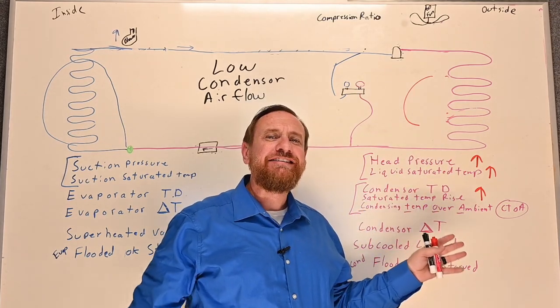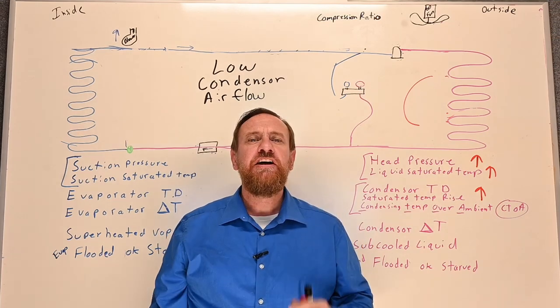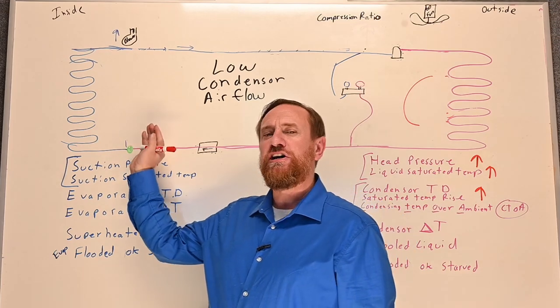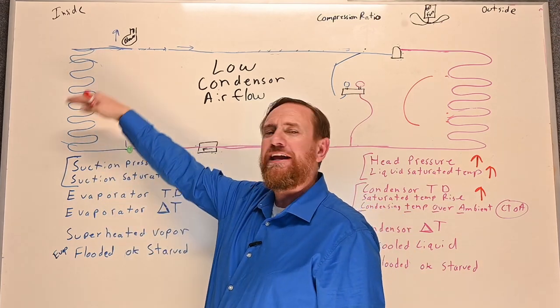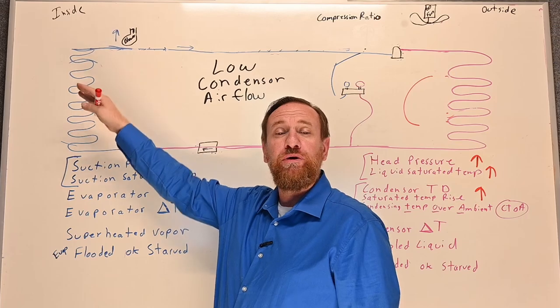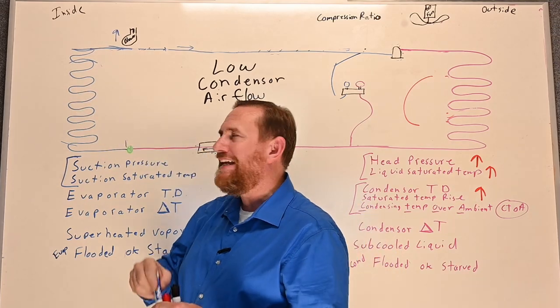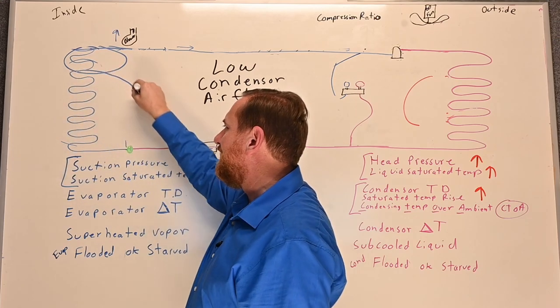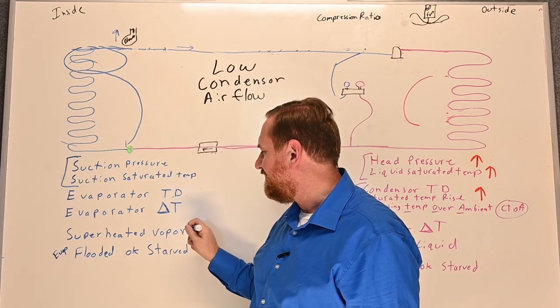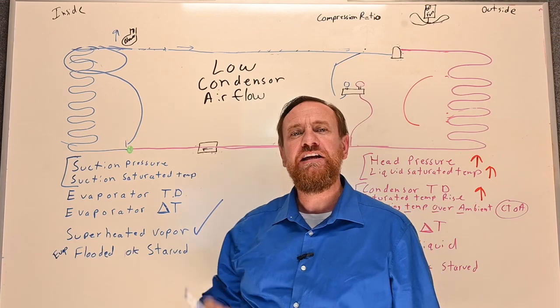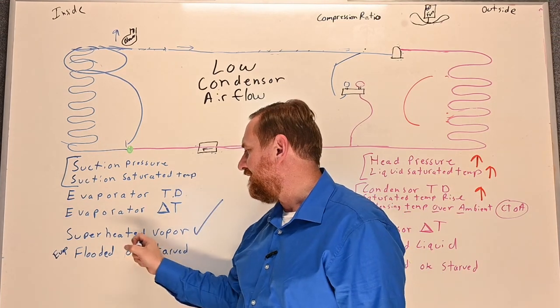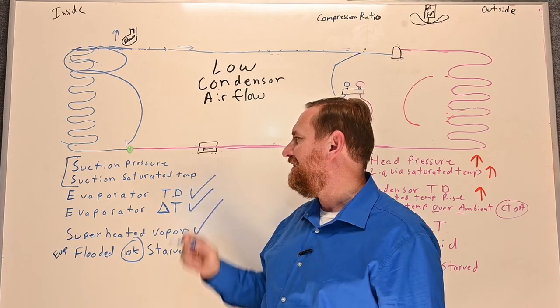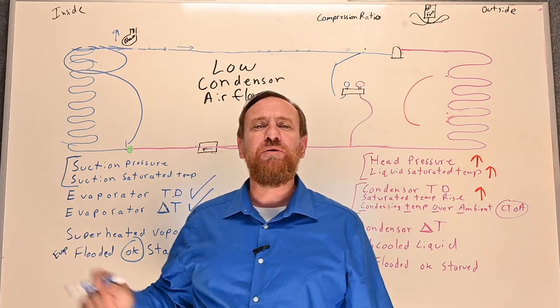What happens next really depends on our metering device. First, let's look at a thermostatic expansion valve (TXV). The TXV's job is to maintain the right amount of superheat in the evaporator coil. It's going to keep the right amount of superheated vapor, which means it keeps the same amount of saturated refrigerant. The superheated vapor with the TXV should be spot on, which means the evaporator coil is going to be okay — you'll still have a good delta T and a good TD.